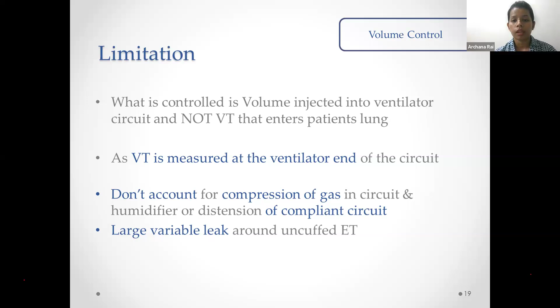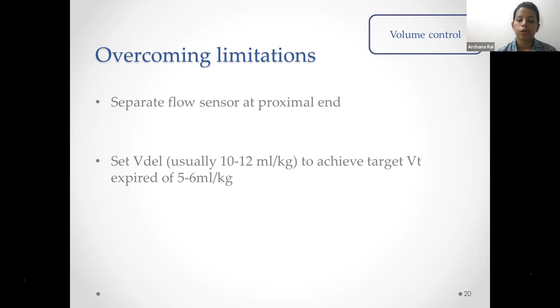To overcome these limitations, a separate flow sensor can be used at the proximal end. Another troubleshooting step is to target an expired VT of 5 to 6 ml per kg. We can set a tidal volume delivery of usually 10 to 12 ml per kg, so that we can get an expired tidal volume of 5 to 6.